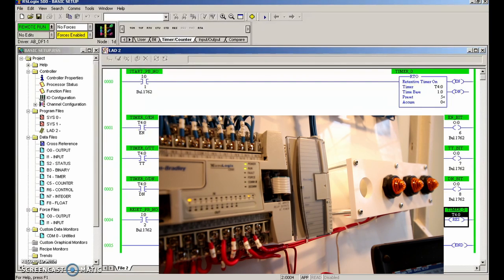But I'm going to stop at a count of 2 and we'll see what happens. Pressing the button now, 1, 2, let it go, and it retains that value. Okay, so it's an on delay timer that retains the actual value. Okay, as soon as we let go of that push button, then the done bit goes right back to its rest state. Okay, we'll keep going up to 5, 3, 4, 5. Beautiful. At that point, I'm going to let go of the push button.